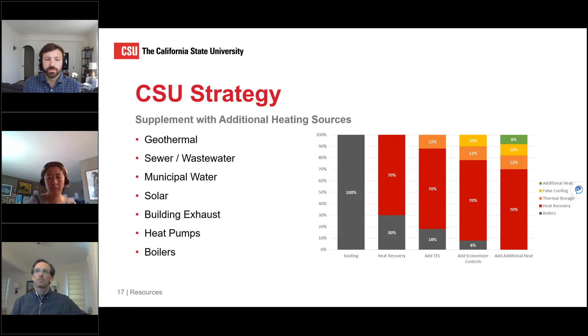Part of the way this can be more economical is to reduce heating hot water temperatures. So that's also a critical aspect of the framework: reducing hot water temperatures helps to reduce distribution losses. It also supports heat pump technologies, which can only supply at lower temperatures, with air source heat pumps at around 130 and heat recovery chillers around 170 to 175. It also improves the efficiency of those. So for example, an air source heat pump with 50-degree air outside can have a 25% savings if we can reduce that water temperature to 115 from 145.